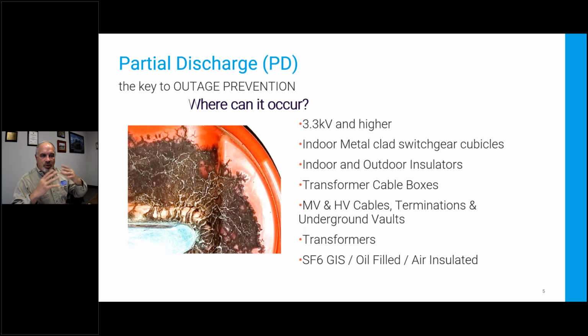So first thing is, where can it occur? Where do we care? The physics says that it can occur at any voltage. In reality, it only occurs at, say, 3.3 kV or 4160, if you prefer to say it that way, and higher voltages. So don't be doing PD at your 480 and 1,000 volt levels. Stick to your 4160 and higher. It can occur anywhere you have high voltage and you have an insulator. That kind of means everywhere.